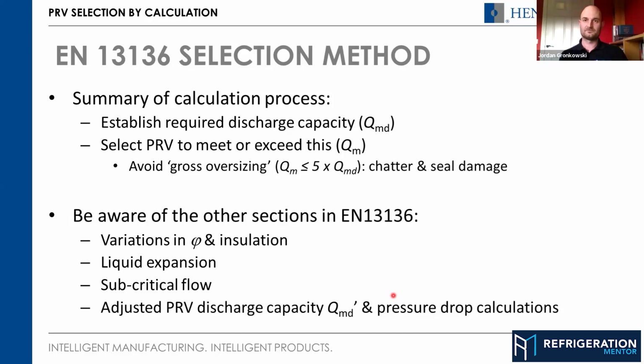So let's just talk quickly, because we know CO2 systems need to be insulated very well because they run colder, with a lot of moisture, which can cause rust and deterioration. So there's a lot of insulation on there. When we talk about various insulation, do you mean the insulating of that flash tank, receiver or vessel, and that will change the selection for the PRV?